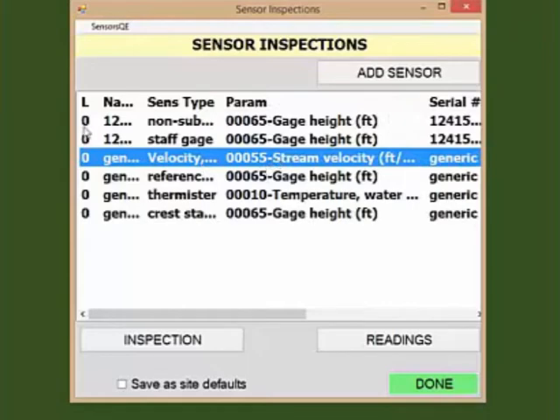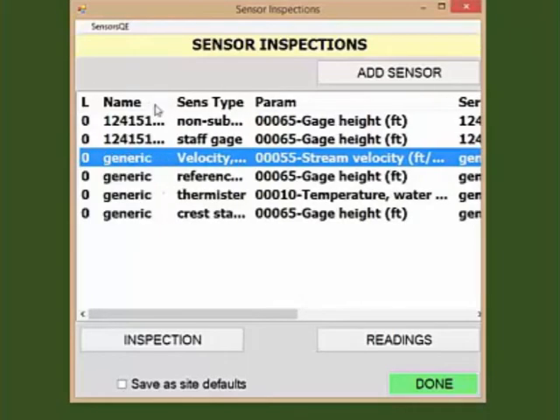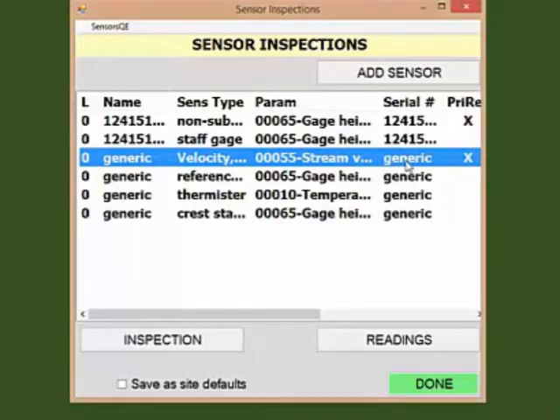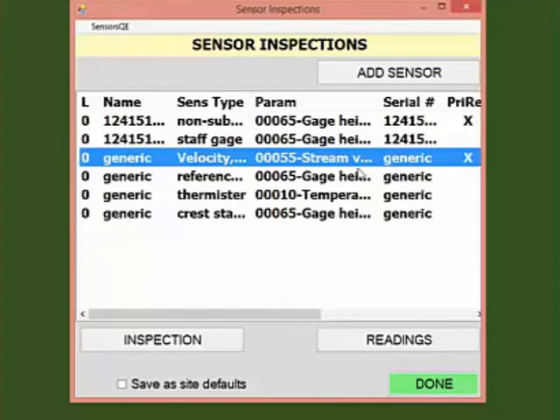You'll note that in my case, the sensor name and serial number are both set as generic. These are set as generic in SiteVisit, so I'm going to leave them as is so there are no conflicts when uploading data to SiteVisit, especially if I ever exchange ADVMs at the gauge. Note that in order for sensor information and readings from the SWAMI file to successfully load into SiteVisit via the loader, the sensor setup information must match exactly between the SWAMI and SiteVisit for that particular gauge.